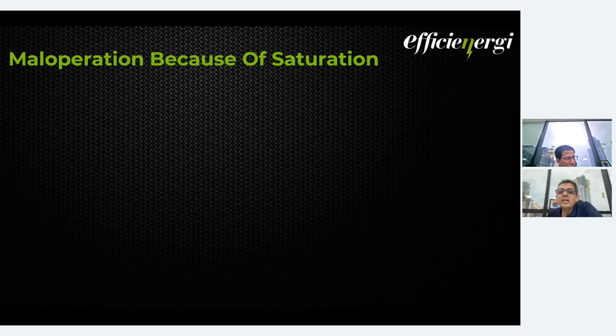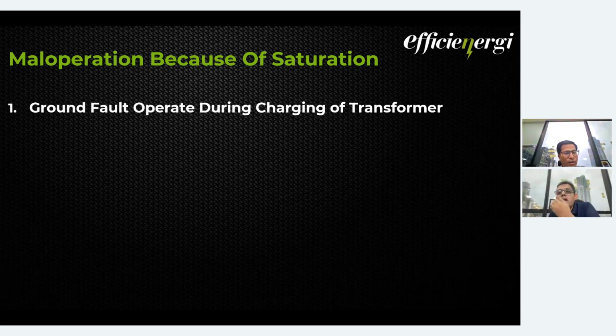I think now we get into some real case studies, after a lot of theory, which Prasad has deep-dived into. Let's get into some practical cases of why maloperation happens due to saturation. The first is something we hear very often: ground fault protection operates during charging of the transformer. The solution is second harmonic blocking, but most people do it in the phase fault and activate phase fault second harmonic blocking. But in the ground fault, how should the current get reflected? Because in the transformer primary, we normally use a residual type of scheme for ground fault detection. This is one case that we normally hear a lot.